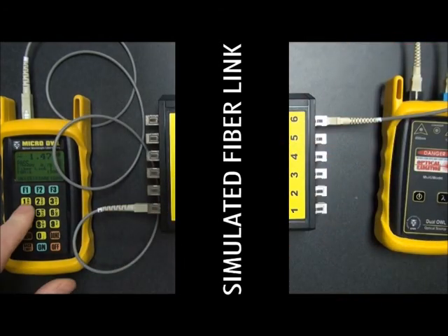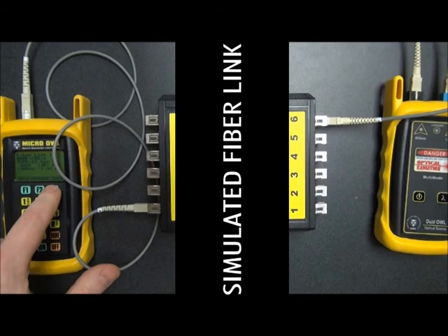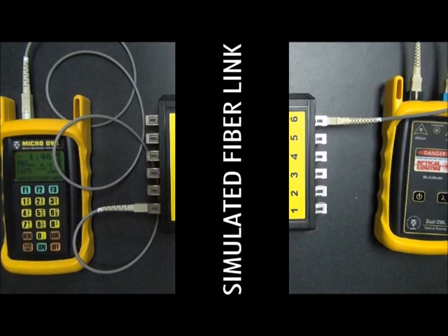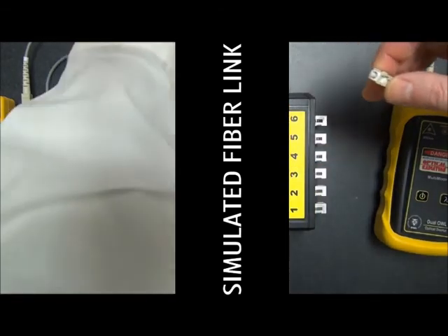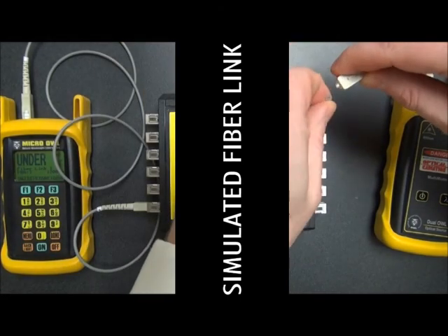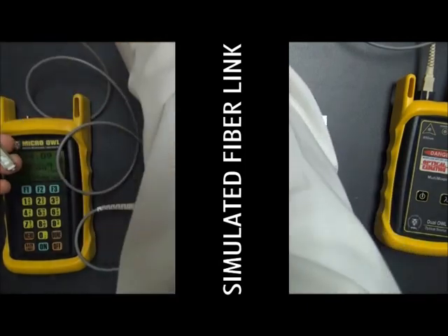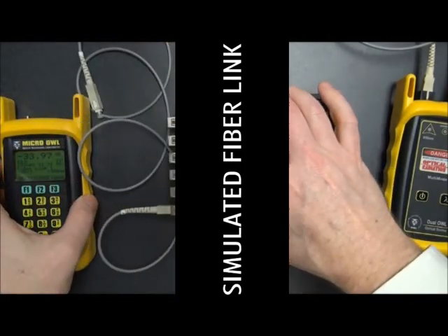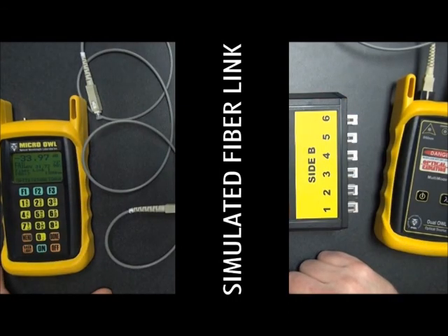And finally we store a reading for fiber number 6. Now, as you can see, we have passed at all of our readings. Both 850 and 1300 nanometers are passing. So we're satisfied with those results. We can disconnect our testers from the link under test, as such here. And then we can take our micro OWL to our PC to download our test results.